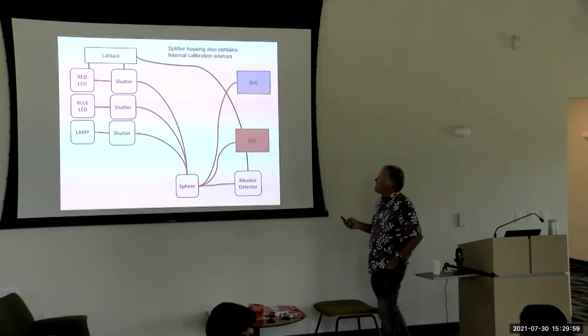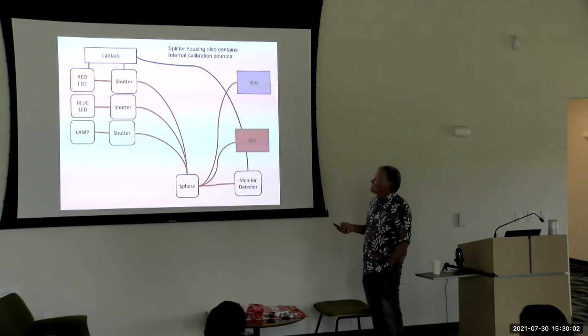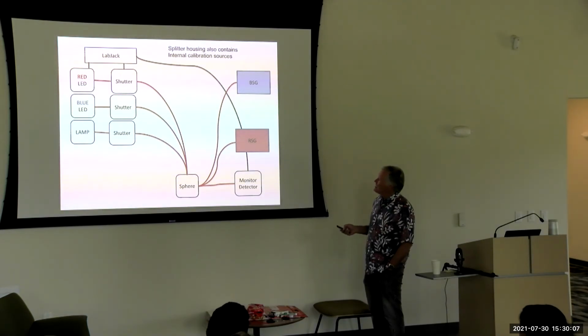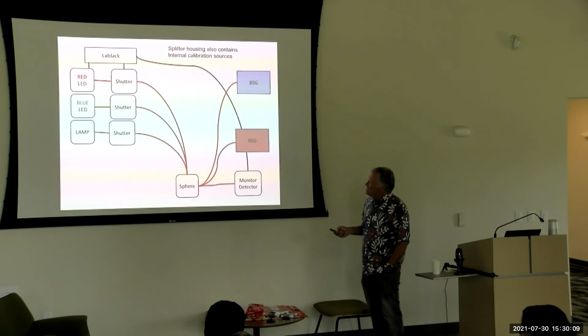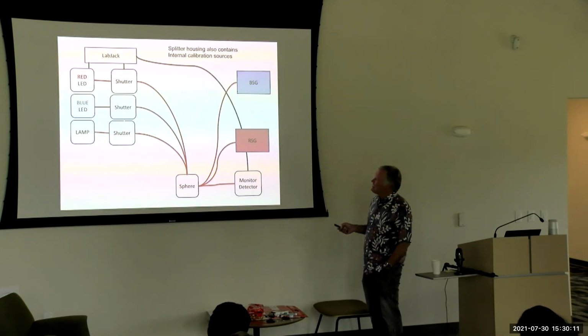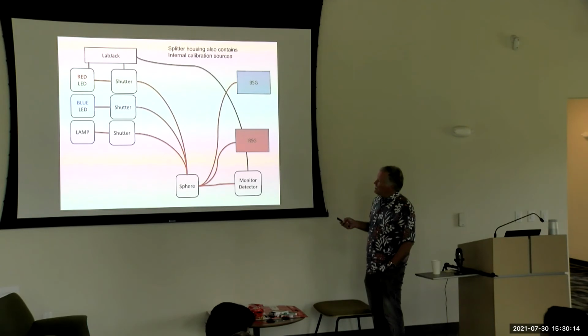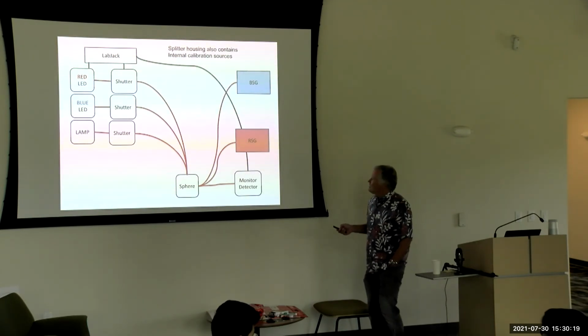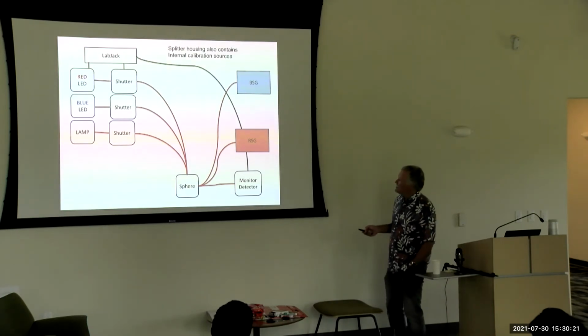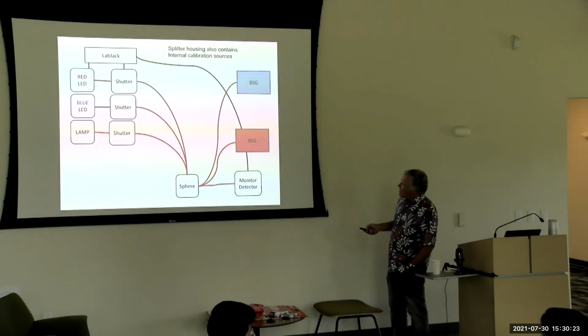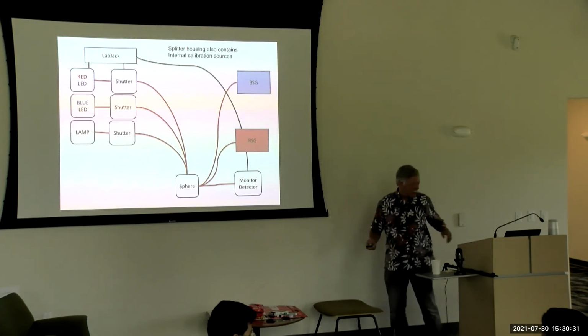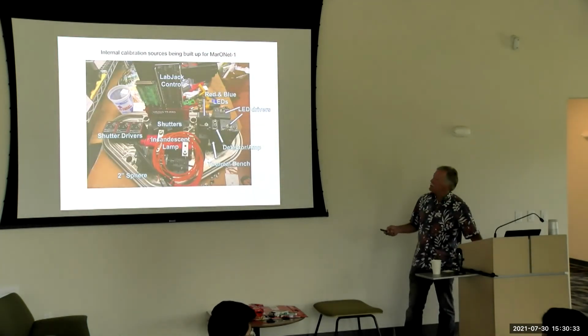Also inside the splitter housing are our internal calibration sources. We have a red and a blue LED, and then a lamp. They each have shutters, so you can independently turn the lamp on, let it stay stable, and all the LEDs stay stable, and just choose which one you want to look at. They go into an integrating sphere. So you have the red and the blue spectrometers with the integrating sphere. There's also a monitor detector, so they have all these calibration sources.